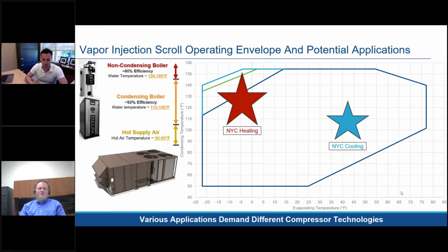This first slide is really going over the different applications that we have and what we target with heating with scroll compressors. You can see the blue areas, your typical cooling conditions, and then the big red star is what you're going to see for typical heating applications. The evap temperature is the saturated suction temperature on the bottom, and on the left, the vertical axis is the condensing temperature, which is your saturated discharge temperature. Typically, you have roughly a 10-degree delta T between your ambient outdoor temperature and the temperature the evaporator is going to run at.